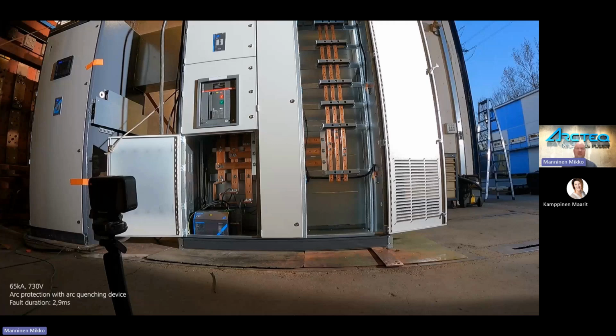I can actually draw here something that the arc is ignited here. Remember, 65 kiloamperes. We have some point sensors here in this panel, quite few. And arc flash relay, which is here, is measuring the current, and it's also detecting the light from the arc ignition. Its main purpose is to trip fast, and that is always the main purpose for arc flash relay. So you can detect, you can protect, and you can mitigate. So sensor is for detecting, and also different current monitoring ways are also detecting.